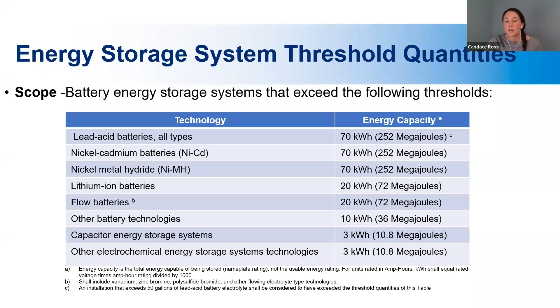Next, systems will have to perform a hazard mitigation analysis. There are a couple of key regulatory requirements which are important to discuss for these larger battery systems. When we talk about these larger systems, the 2020 code imposes stricter requirements for systems that are over 600 kilowatt hours. Once again, these tier 2 systems need to meet this. The first key requirement is the hazard mitigation analysis, which is required for tier 2 systems, and the study is done to evaluate consequences of failure modes seen here on the left side of the screen. This analysis will evaluate the consequences of failures if there's a thermal runaway in a single energy storage rack, module, or unit, failure of any battery management system, failure of any ventilation system, and voltage surges.